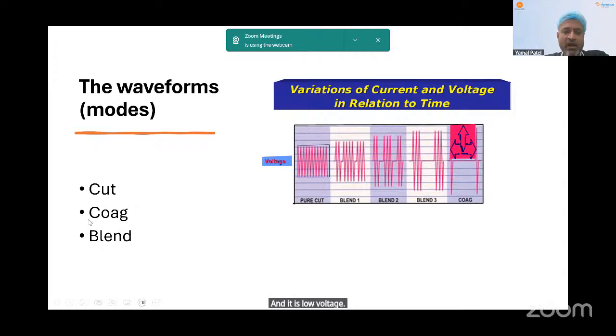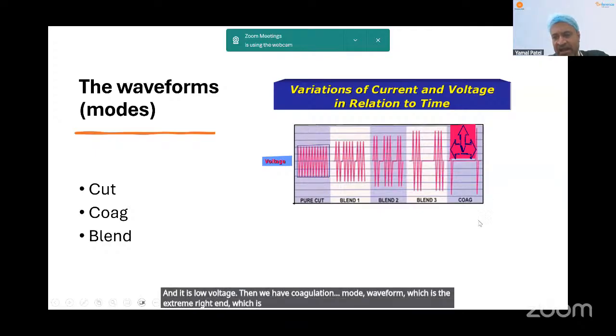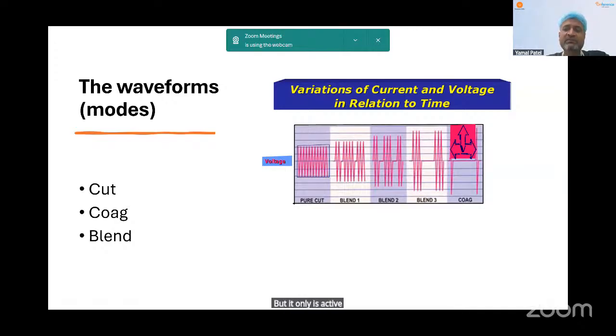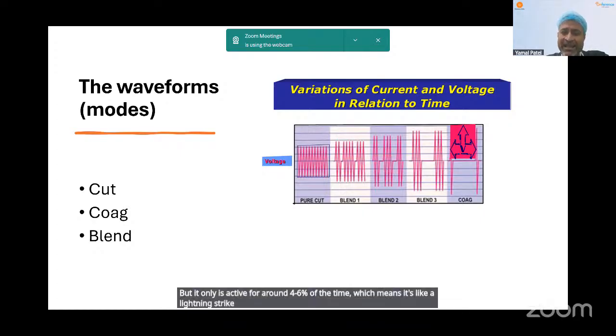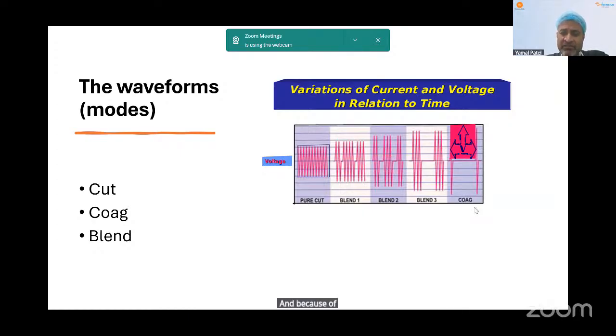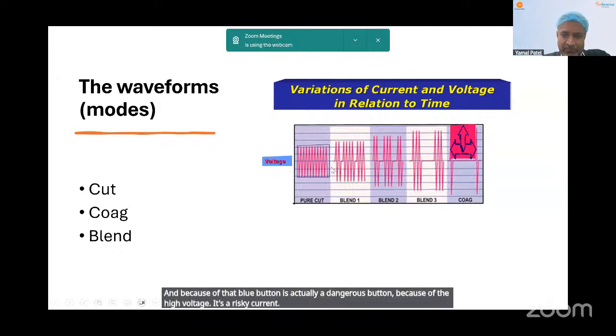Then we have the coagulation mode waveform, which is the extreme right end, which is very high on and off, and it is going as high as 6,000 to 9,000 volts. But it is only active for around 4 to 6% of the time, which means it's like a lightning strike on and off. Because of that, the blue button is actually a dangerous button because of the high voltage. It's a risky current.